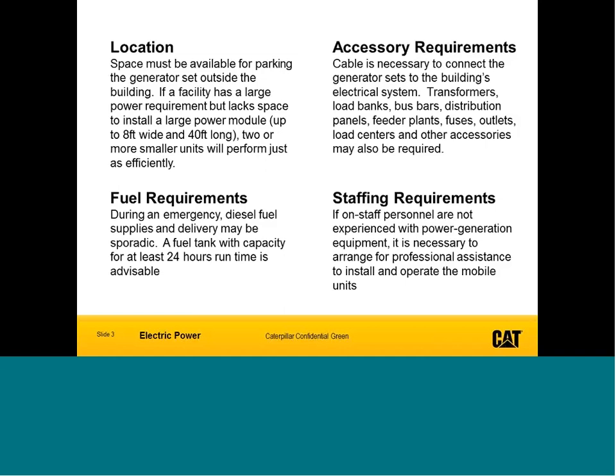In terms of bringing generator cables into your circuit breaker, one thing I'd recommend is installing some sort of weatherhead or cable access door in an outside wall of your facility that can be closed when not in use. This way you won't be required to route cables through windows, doors, or other areas that should be closed in non-working hours, whether for safety, theft, or weather concerns. It's something that's often not thought about, but it's a simple thing you can do that makes your life and operation function much simpler.